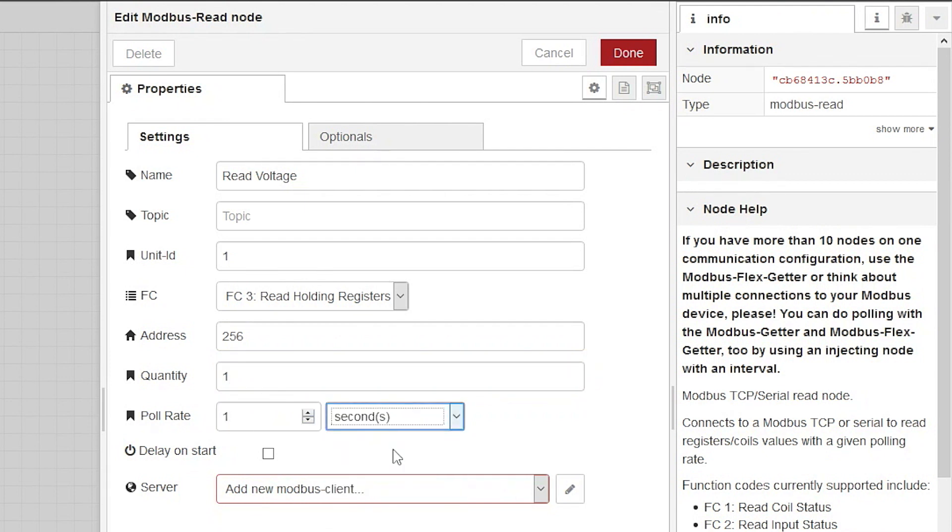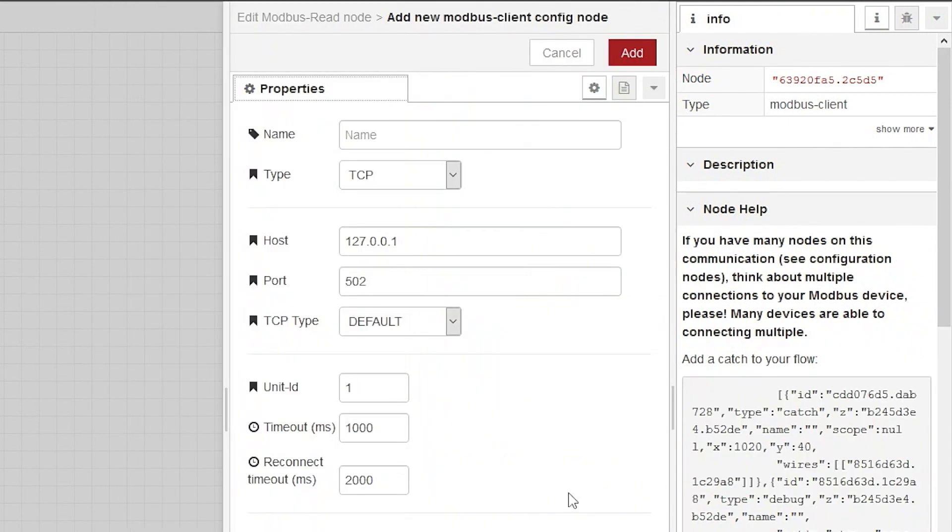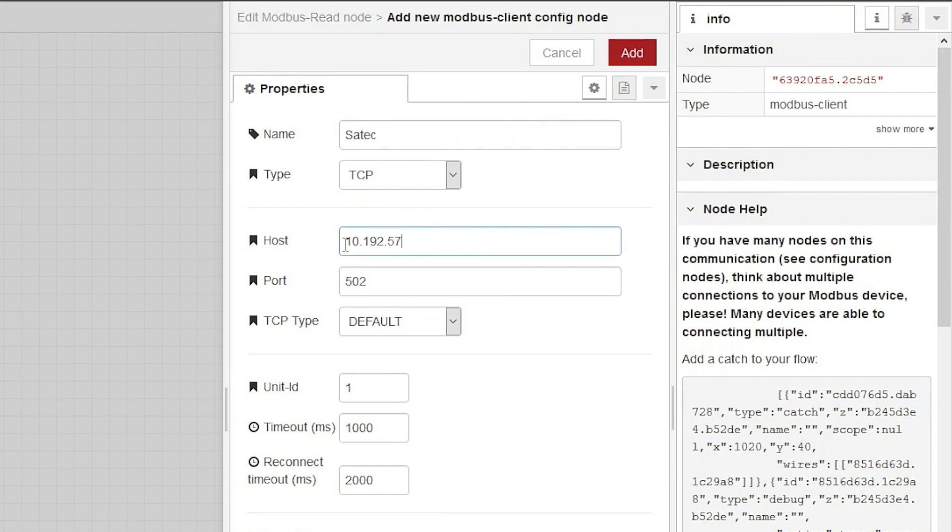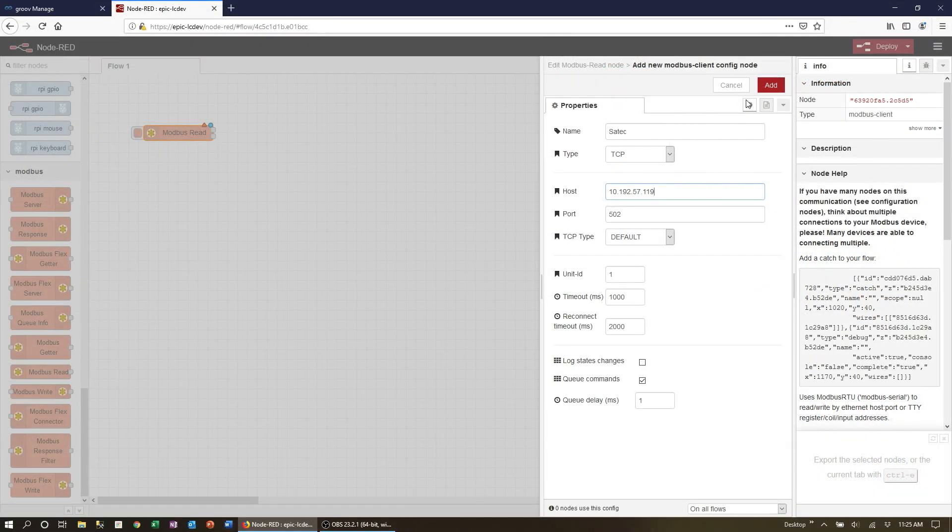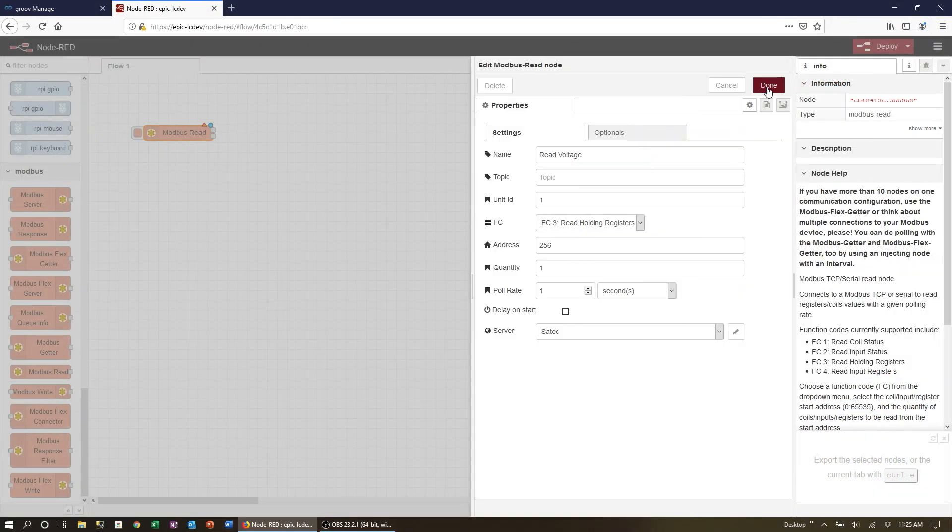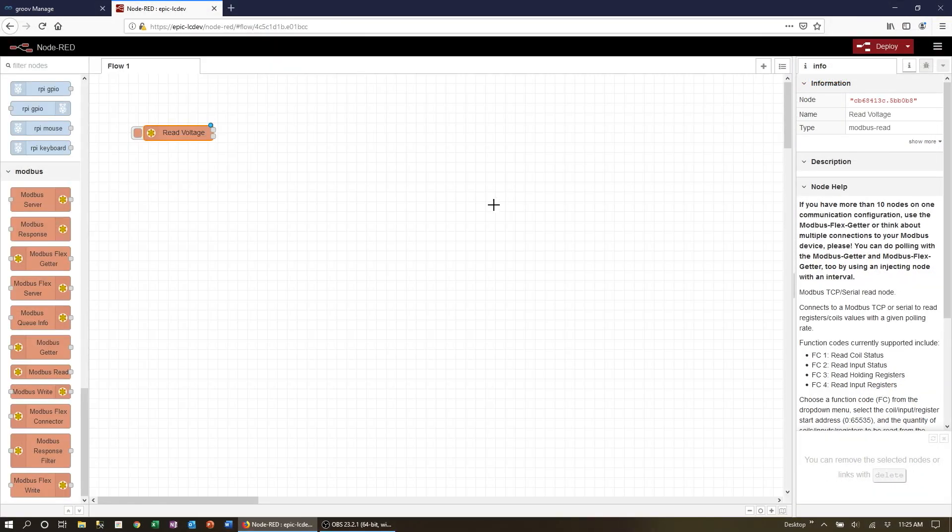We next need to configure the device. The name can be anything, I'm going to call it simply SATEC. Type is TCP. And now we put the IP address and in my case the default Modbus TCP port number of 502. Both of these settings are configured on the Modbus device you have so they should match your configuration exactly. That's all the settings we need to adjust here for the device.